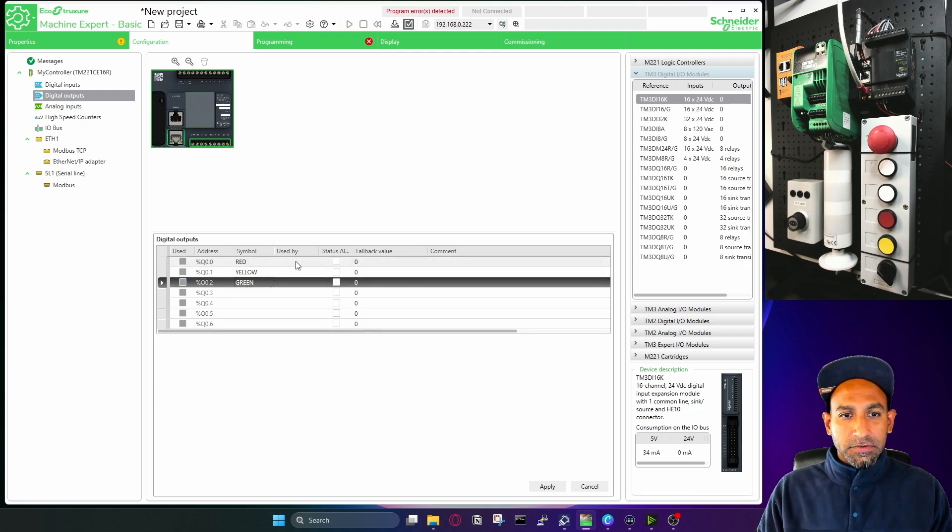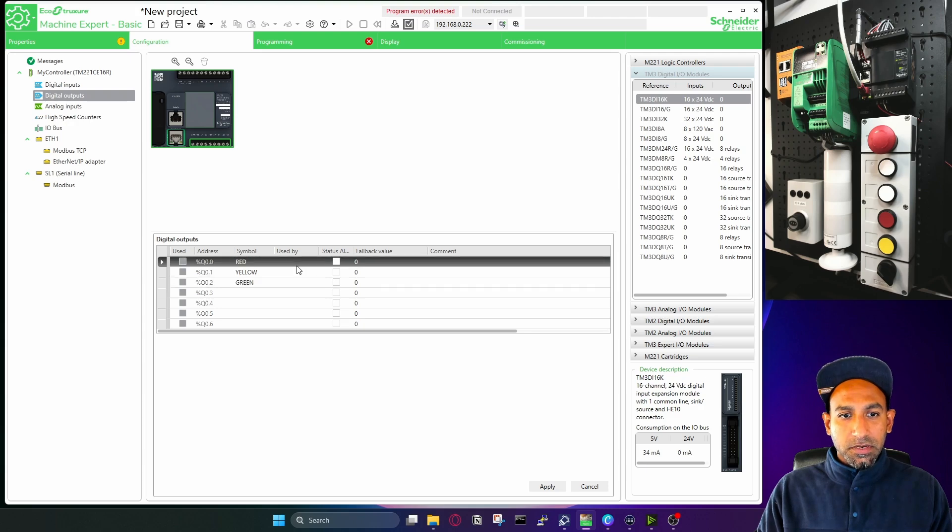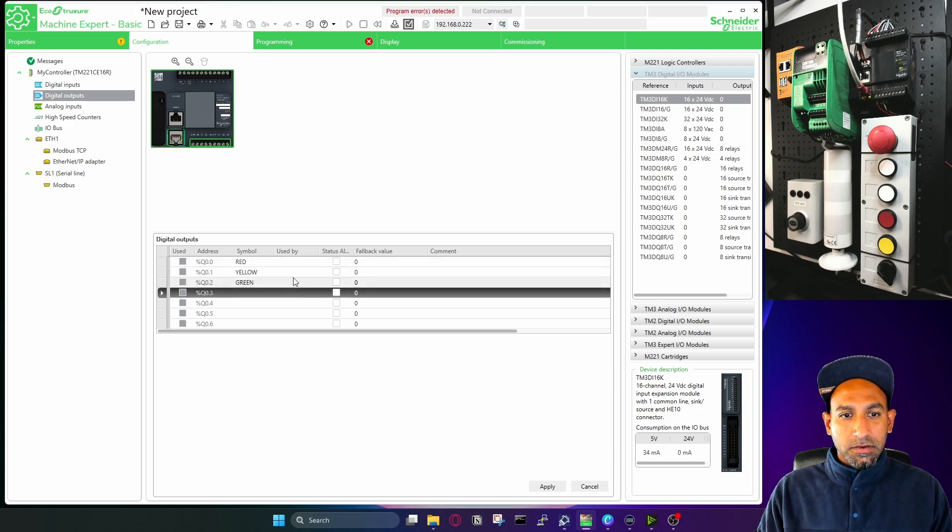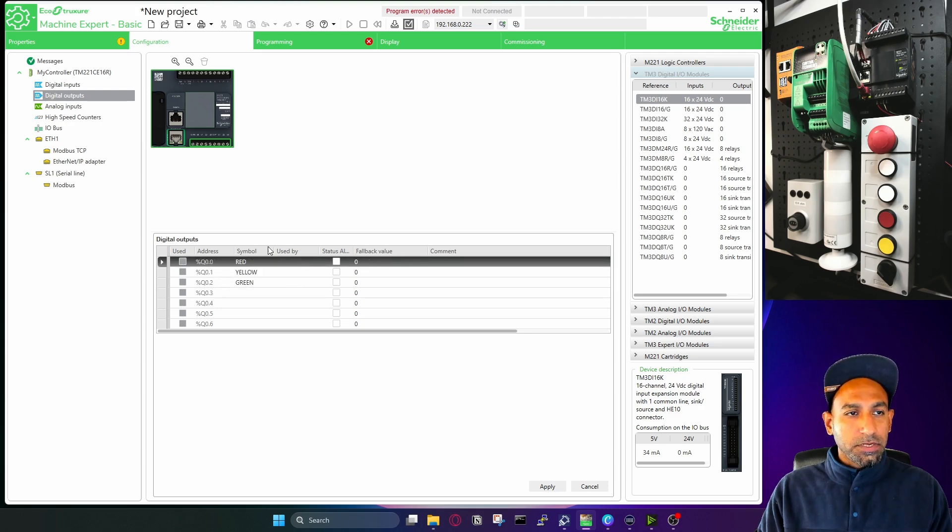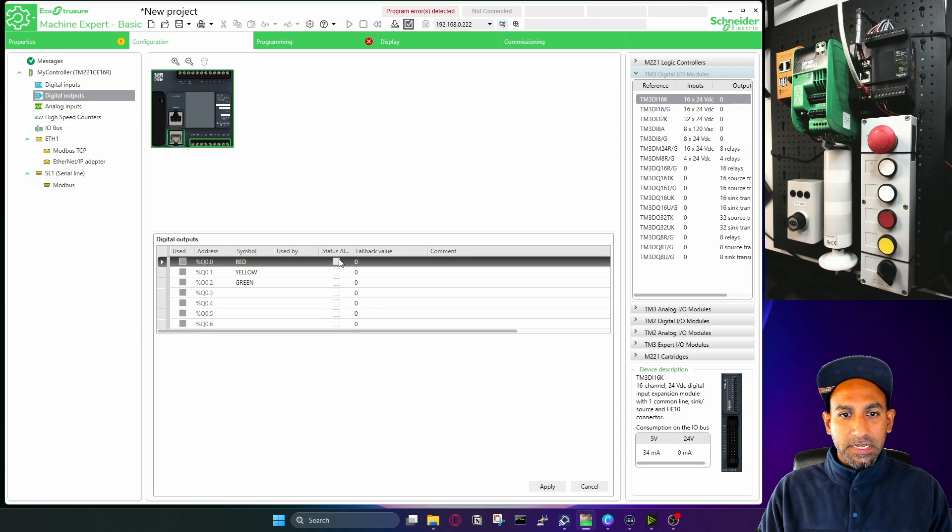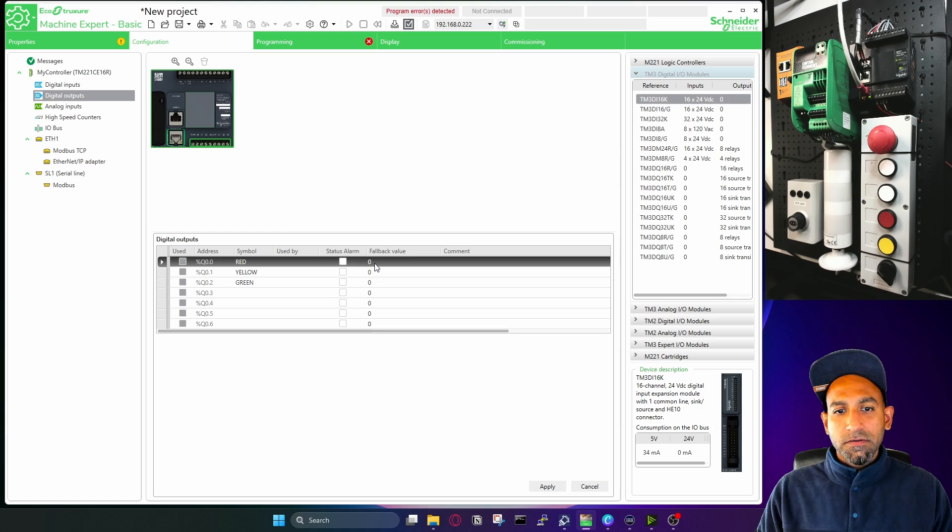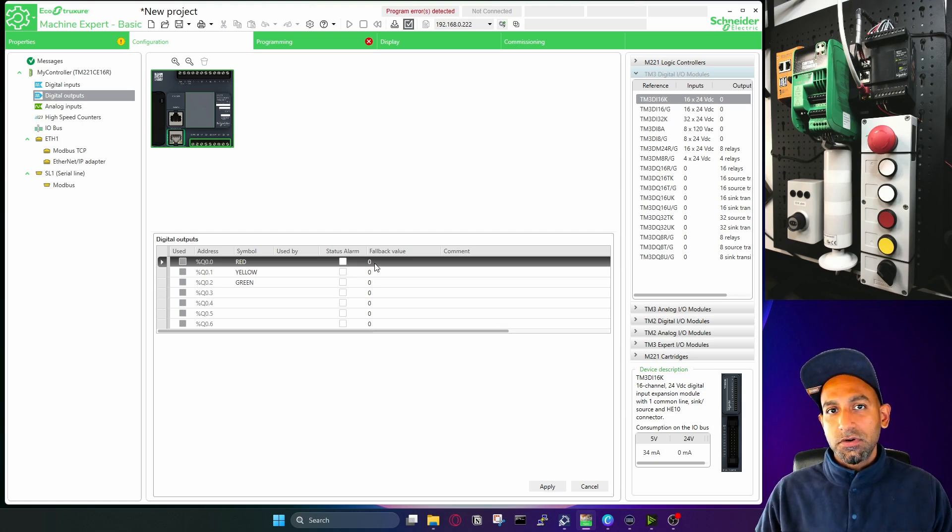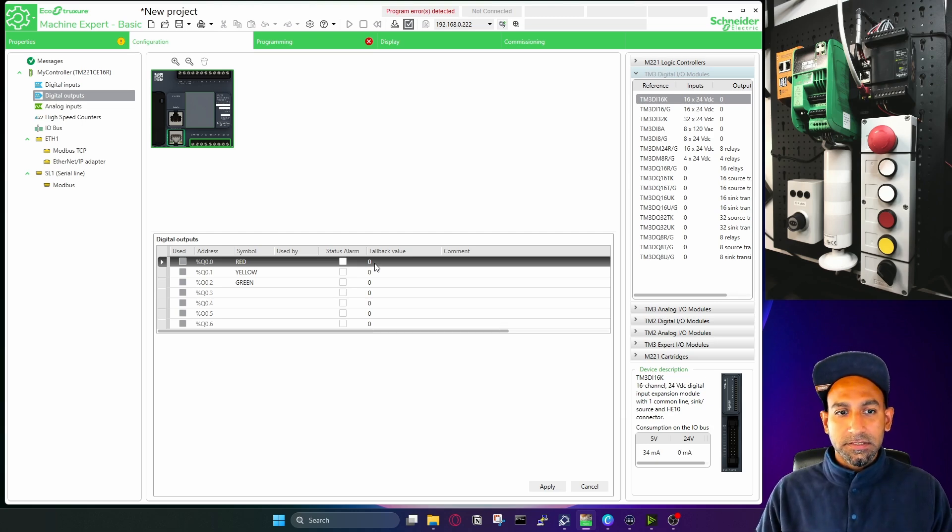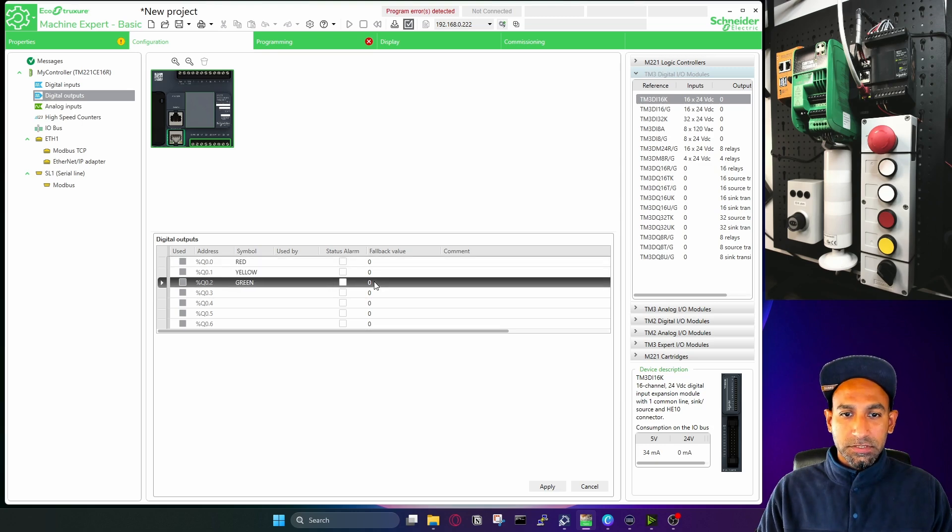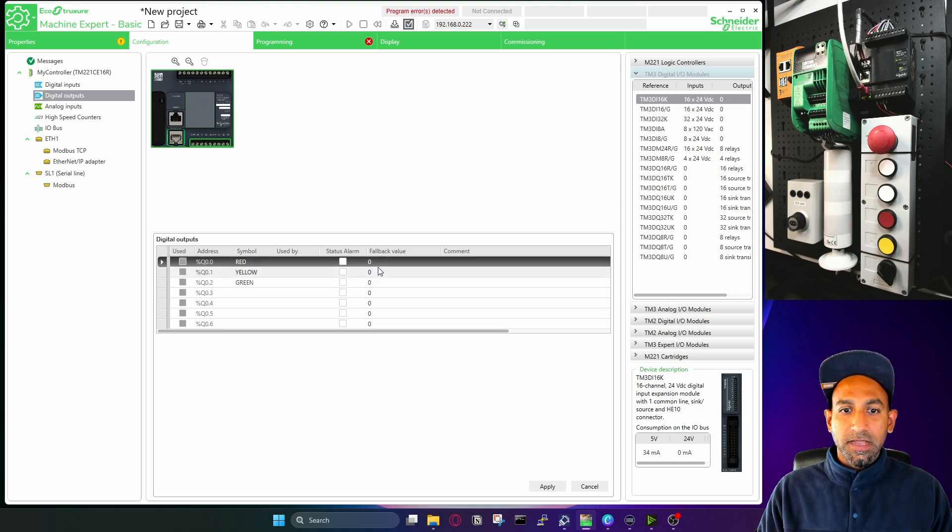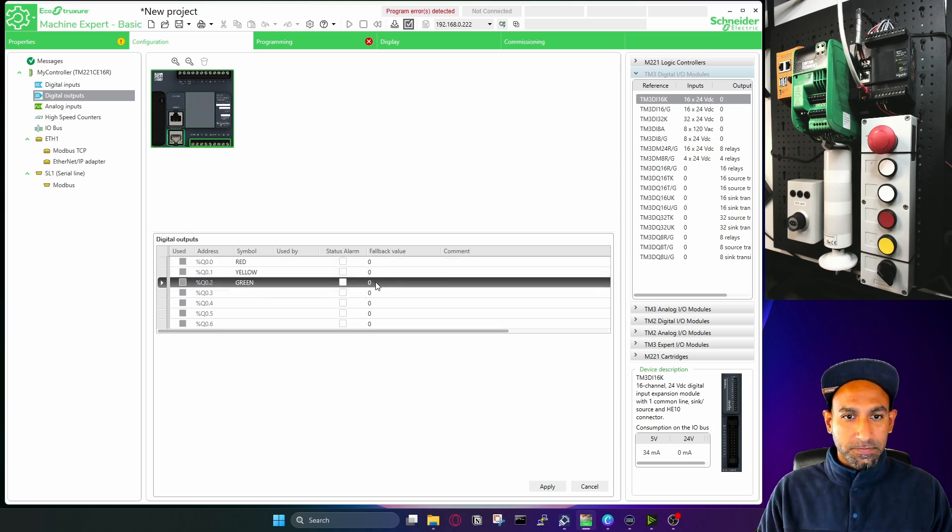So I added three outputs, and it will tell you what is used by which POU is using it. And the status, you can see here status alarm. Fallback value is zero. Fallback value means if the PLC goes to an error status or a halt status, what should be the value of the output? It is by default false.